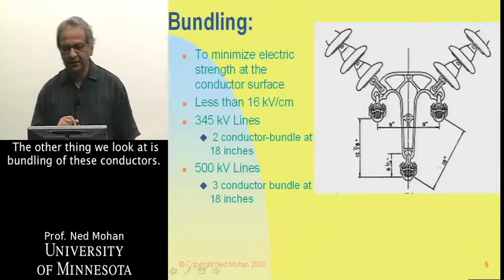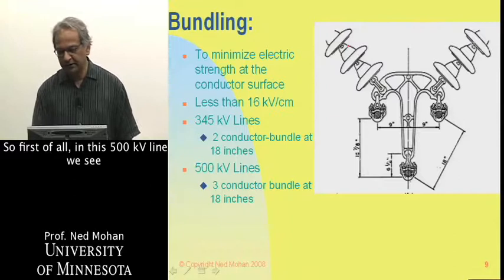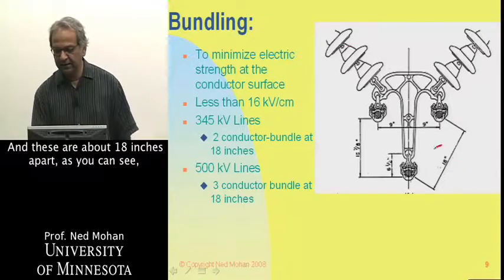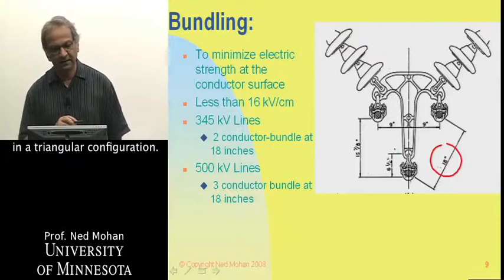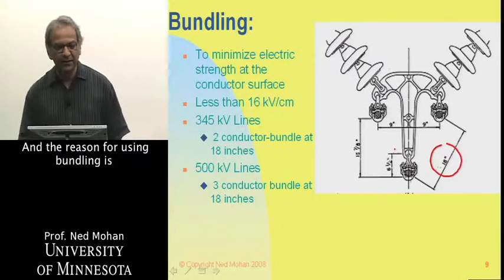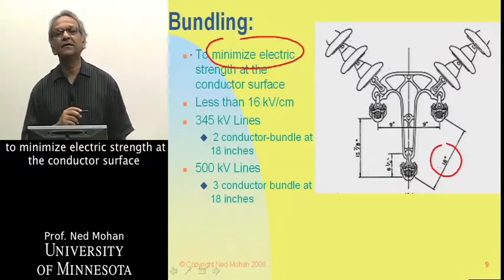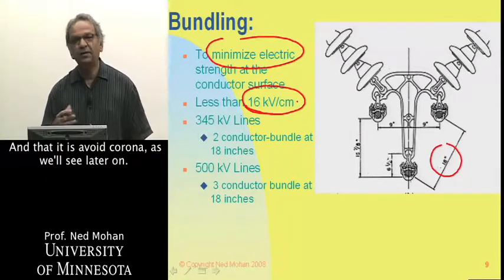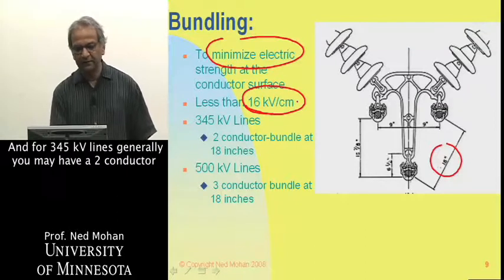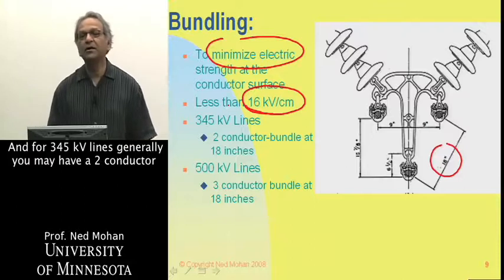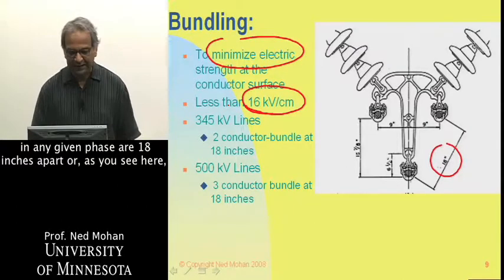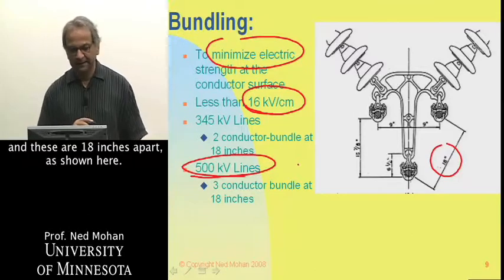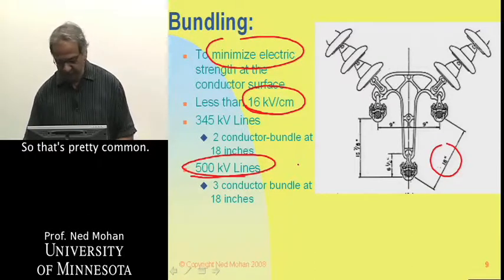Another topic is the bundling of conductors. In this 500 kV line, each phase consists of three conductors in a bundle, about 18 inches apart in a triangular configuration. The reason for bundling is to minimize electric field strength at the conductor surface to less than 16 kV per centimeter, in order to avoid corona. For 345 kV lines, you generally have a two-conductor bundle with conductors 18 inches apart, while for 500 kV lines you have a three-conductor bundle also 18 inches apart.